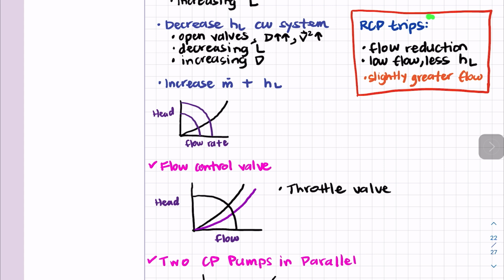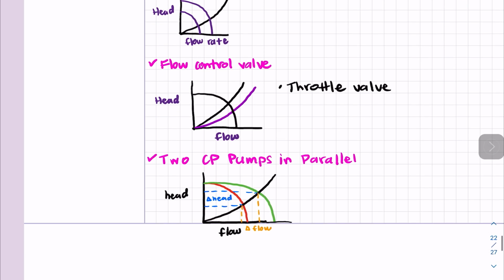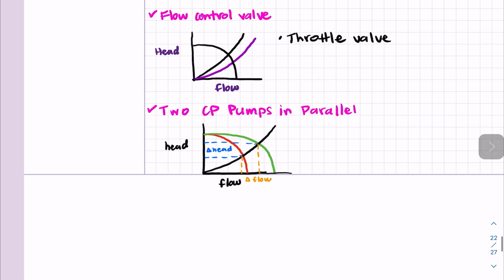So when we have reactor coolant pump trips, remember we have a reduction in the flow, so we're reducing the velocity. So low flow means less head loss. A slightly greater flow is also going to affect this, but we will go over it when we take a look at the example. Also, we go over flow control valves. Here it tells us what happens if we throttle the valve. If we throttle the valve more, we decrease the flow, but we increase the head. We will go over that as well.